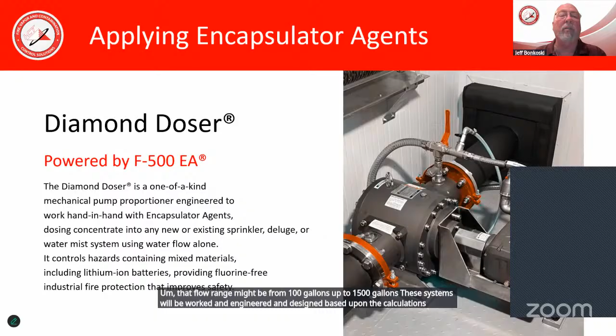What's nice about these is if you have just one or two sprinkler heads that go off, or you have 10 sprinkler heads that go off, the system isn't designed to be set at one specific flow rate. It has a large flow range, maybe from 100 gallons up to 1,500 gallons. These systems will be engineered and designed based upon the calculations, flow rates, and information that you share with us.